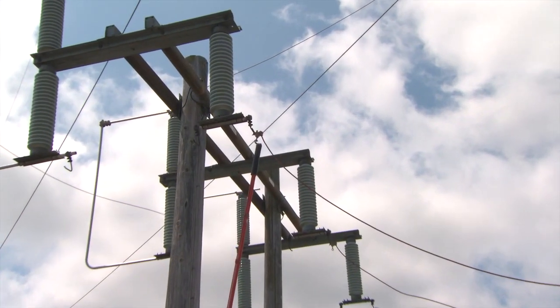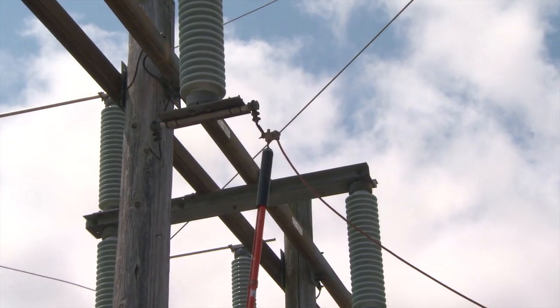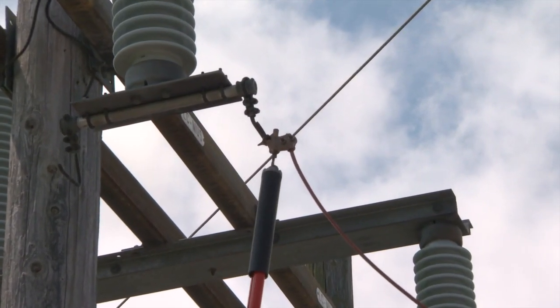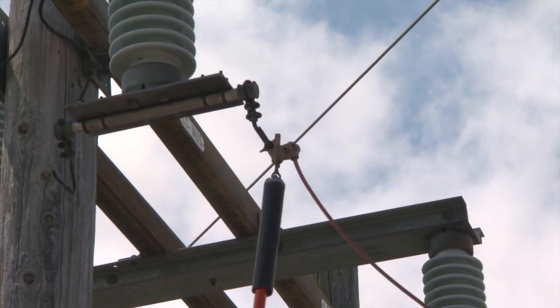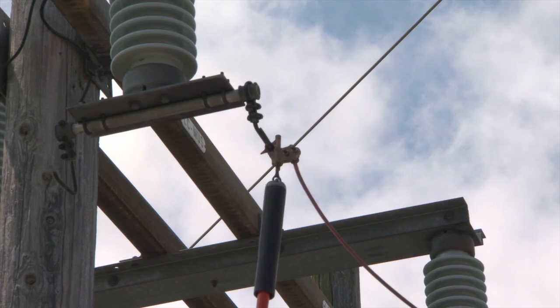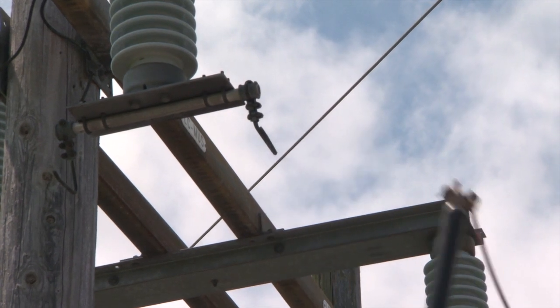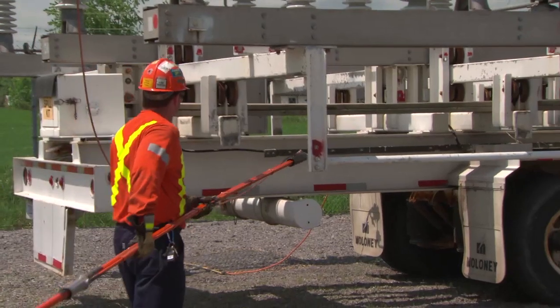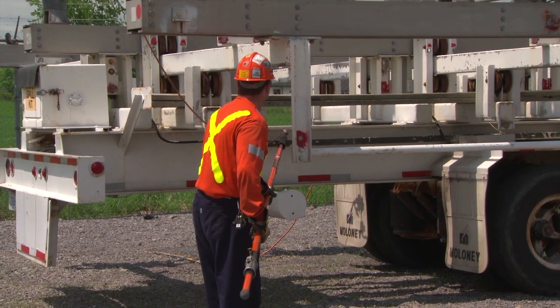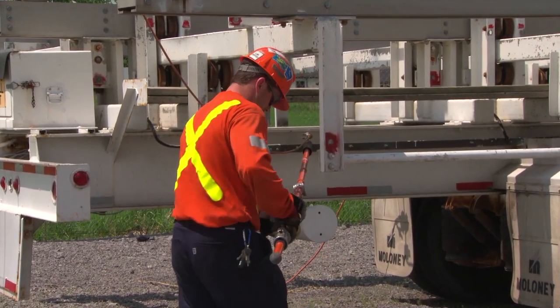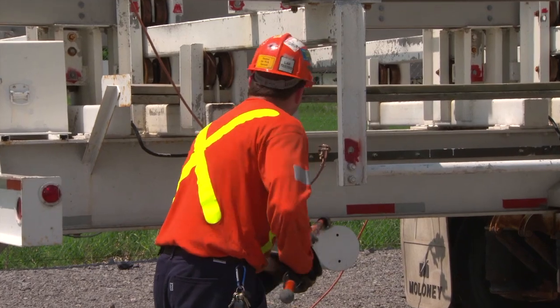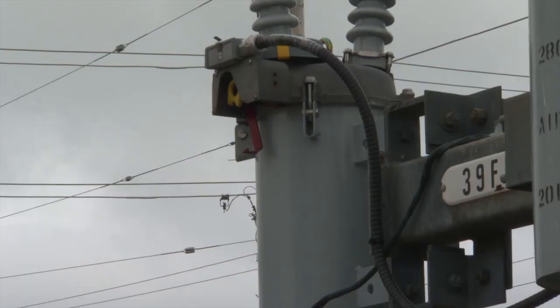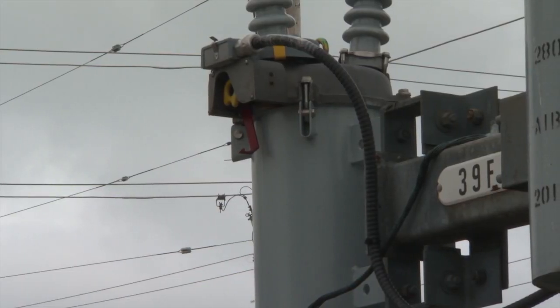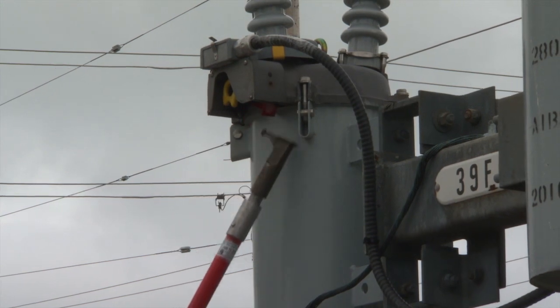Remove the high voltage leads from the MUS switch jaw. Control the lead completely to the ground and park it on the MUS. The neutral cable is removed last. Place the DS reclosers in the reclose position.